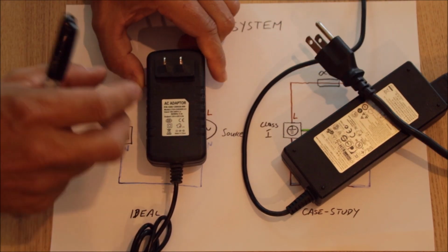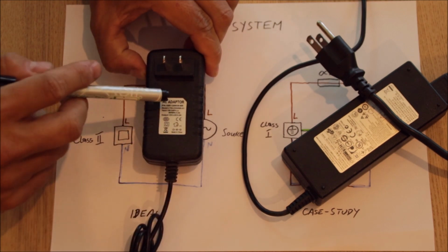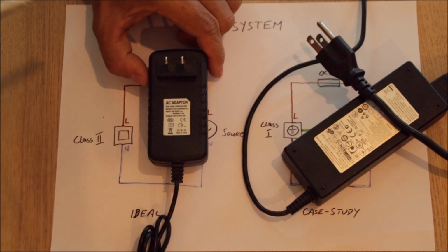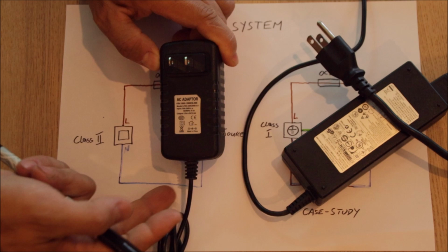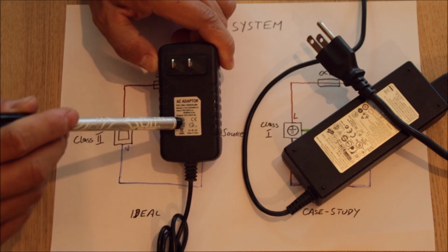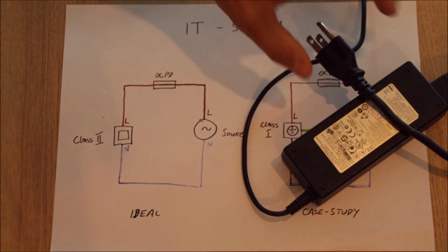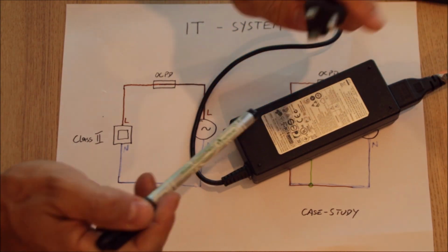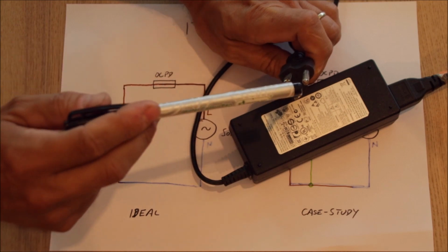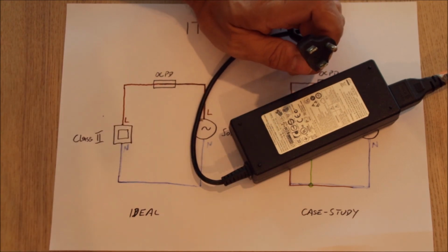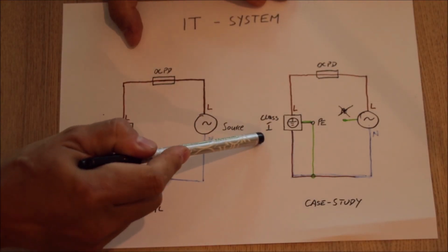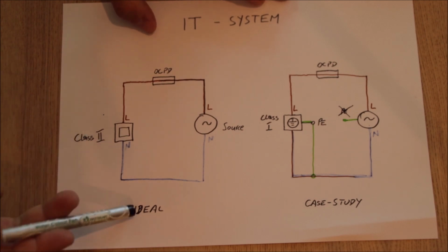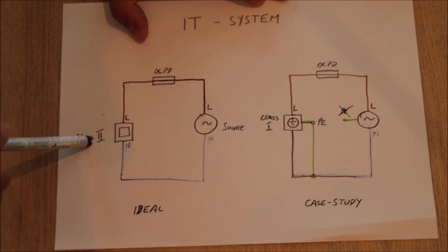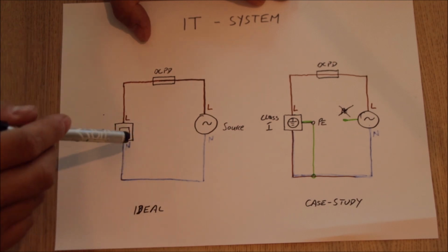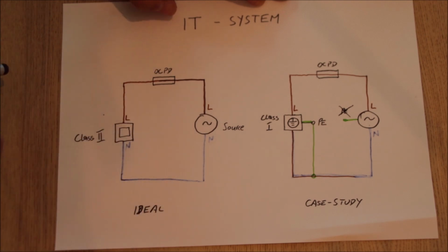Class 2 means the appliance is designed in a way that you can never accidentally come into contact with any of the active wires. So we have an L and an N, and that's already it. Usually when you have a class 2 device, you will have the symbol on it. Class 1, we don't have a symbol, but you can see it because we have an extra PE, the protective earth wire, on this plug. So class 2 does not require earthing, class 1 requires earthing. Okay, so as I said, in the ideal case, from source to appliance, all the wires in between, everything is perfectly insulated. So the risk of electric shock in a system like this is basically zero.